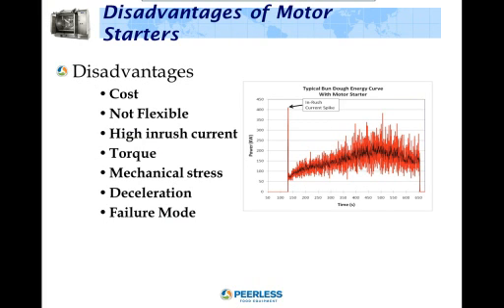Disadvantages of a motor starter. The cost. Two-speed motors cost more than single-speed inverter duty motors. They're not flexible, no ability to fine-tune the process. The higher inrush of current. When full voltage starting, the slip of the motor at zero speed is 100%, and the motor is highly inductive. This results in very high inrush current, 600 to 800%.